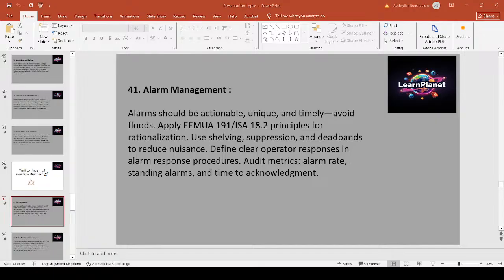Alarms must be actionable, avoid duplicates, and not flood the operator. Rationalization using EEMUA 191 and ISA 18.2 is best practice. Use shelving, suppression, deadbands, and delay timers to reduce nuisance alarms while keeping safety critical alarms immediate. Create clear alarm response procedures and train operators on them. Monitor alarm performance metrics: alarm rate, standing alarms, and time to acknowledge, and continually improve. Example, rationalize repeated transient high temperature alarms by adding a 10-second delay and a specific operator action procedure for persistent trips.